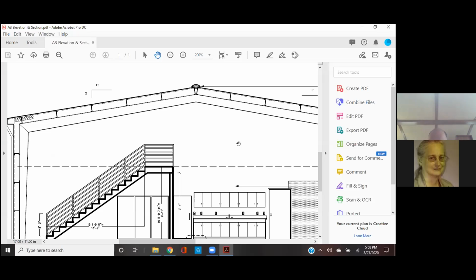Right. So every 30 minutes, you need to move that volume of air. Usually duct sizes are in cubic feet per minute. So if you take that number and divide it by 30 minutes, you should get how much air you need to push through the ducts into that space every 30 minutes. Does that make sense? Yes.